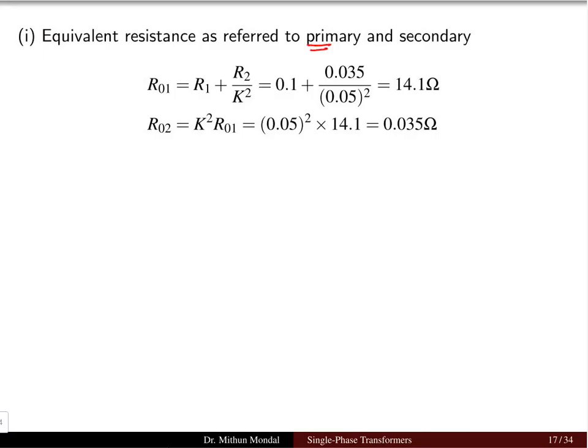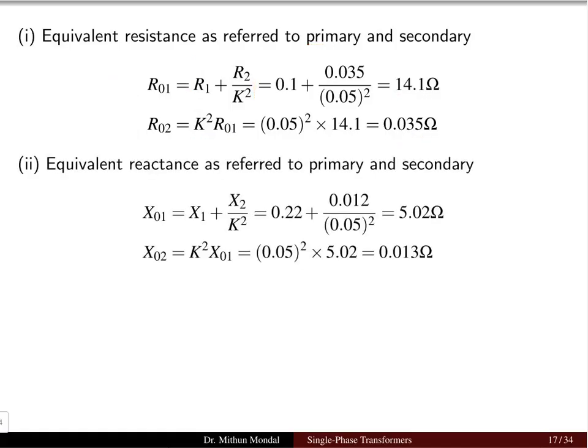So R01 is equal to R1 plus R2 by K square, which comes to be 14.1 ohms. Now R02 we can refer, that is primary can be referred to the secondary side multiplying with K square. So that is 0.035 ohms. Similarly, the reactance on the primary side is equal to X1 plus X2 by K square, which comes to be 5.02 ohms. And the reactance on the secondary side is K square multiplied with the reactance on the primary side, which comes to be 0.013 ohms.